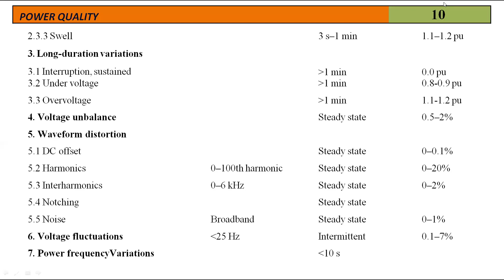Coming to the fifth one, waveform distortion. This is the most occurring power quality problem. In this one we have DC offset, steady state, 0 to 0.1%. The second one is harmonics, and frequency range is 0 to 100th harmonic, steady state 0 to 20%, interharmonics 0 to 6 kilohertz, steady state 0 to 2%, notching steady state, noise broadband steady state 0 to 1%.